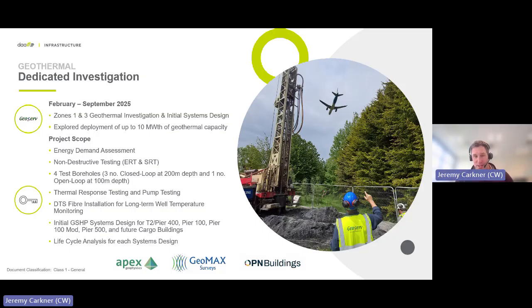That led to siting of specific borehole locations. We did 4 in total, originally 5 in scope but trimmed down for various reasons. 3 were closed loops and 1 was an open loop. The closed loops were at 200 meter depths, and the open loop was at 100 meter depth. The idea was to do thermal response testing on the closed loops and pump testing on the open loop.